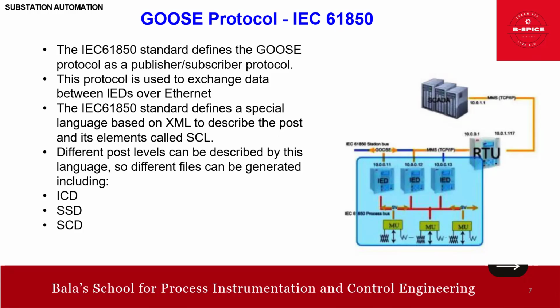So GOOSE is designed to provide ultra fast and reliable communication between IEDs, that is intelligent electronic devices, within the substation. It can transmit the data within 4 milliseconds, which is very crucial for protection and control applications. So that is the beauty of GOOSE. Then data grouping. The protocol groups various types of data, such as status and values, into data sets. These data sets are then transmitted over the network using Ethernet, ensuring that all relevant devices receive the information simultaneously. So that is the beauty.